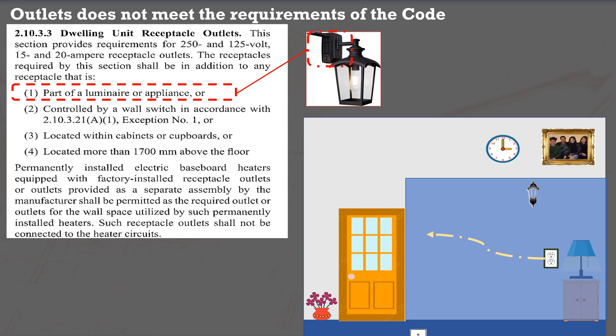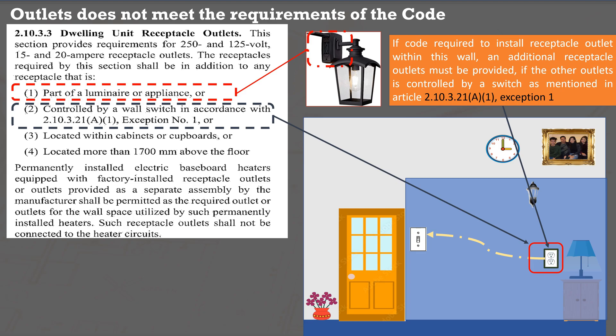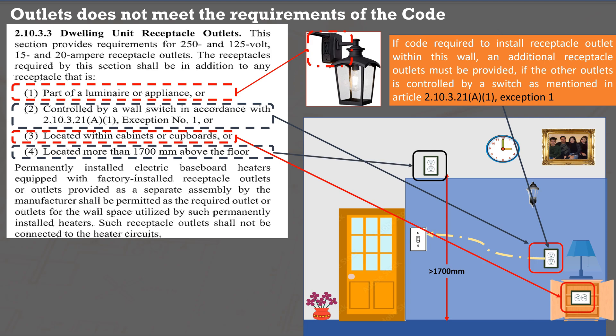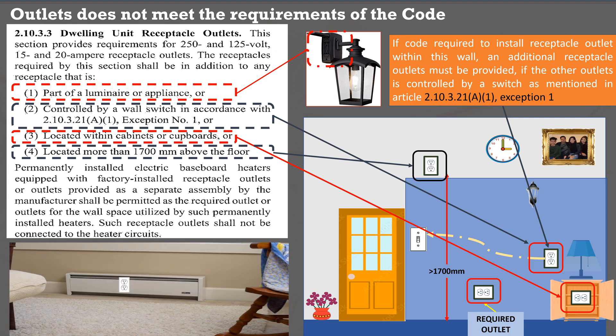If you provide an additional outlet but it is controlled by a wall switch under section 2.10.3.21a.1, exception number 1, this outlet also does not meet the requirements (bullet number 2), and an additional outlet is still required. Further, if an outlet is installed inside a cupboard or cabinet (bullet number 3), it does not meet the requirement. If an outlet is installed at more than 1,700 mm in height (bullet number 4), it also does not meet the requirements, and an additional outlet is required. However, permanently installed electric baseboard heaters with factory-installed receptacle outlets, or outlets provided as a separate assembly by the manufacturer, shall be permitted as required outlets.